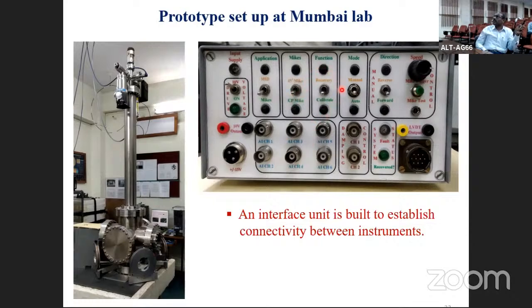You also have functions for recovery mode and calibration mode, which I'll explain later. In addition, you can choose manual or auto calibration; mostly we do auto calibration. In manual calibration, you get full control of the encoder motor mic. This gives the system status, these are the outputs for the power amplifiers, and these are the inputs coming from your optical levers.